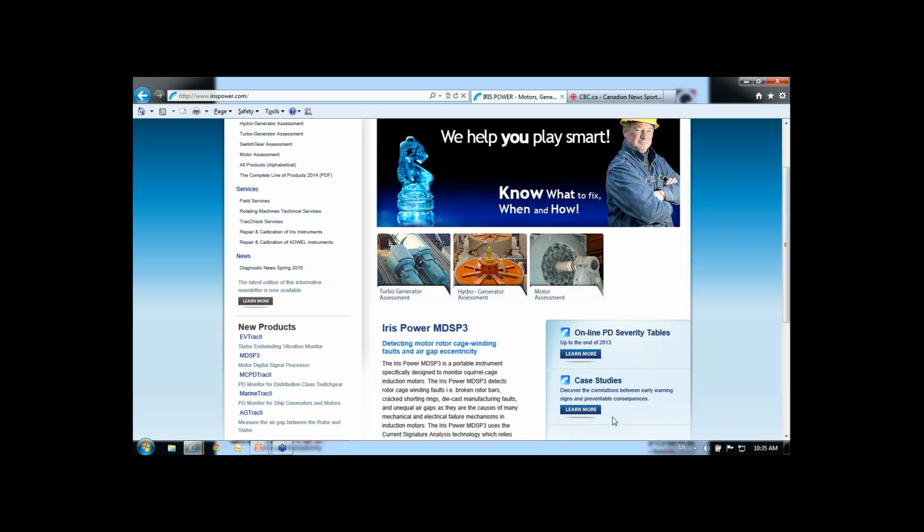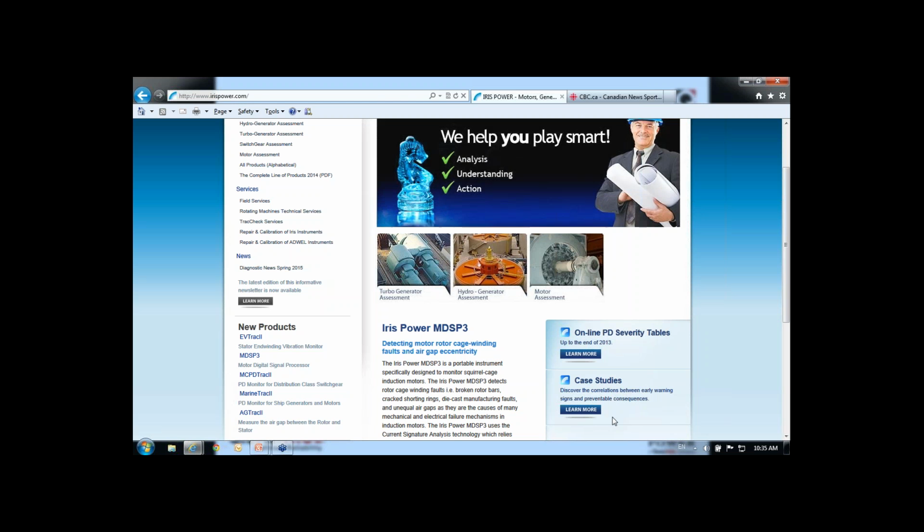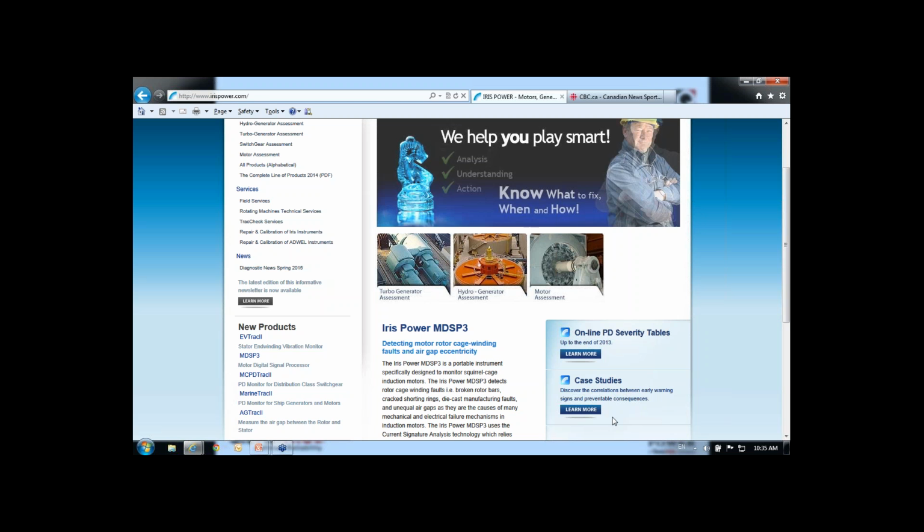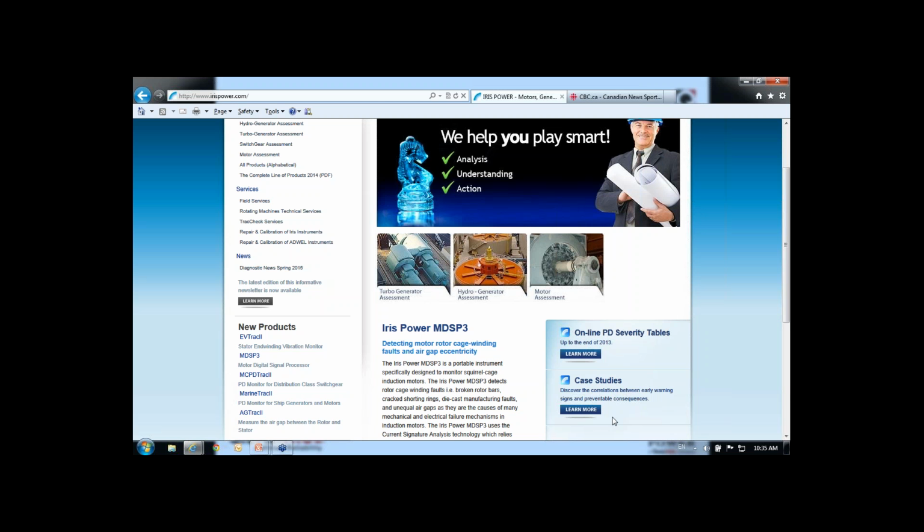That's a difference between relay protection and even some stator fault protection. Stator ground fault relays are not sensitive to the last part of the stator winding unless they're equipped with a third harmonic sensor or a similar method. PD is a process which takes place in the presence of sufficiently high voltage, and if problems are of a mechanical nature and far from the line end of the machine, then no PD will occur as a result, and it will not be detected by the sensor anyway.